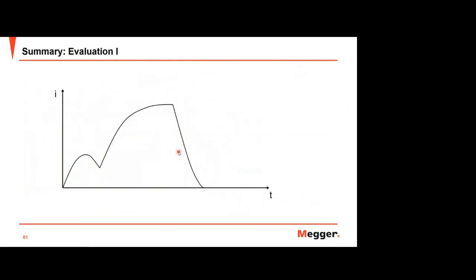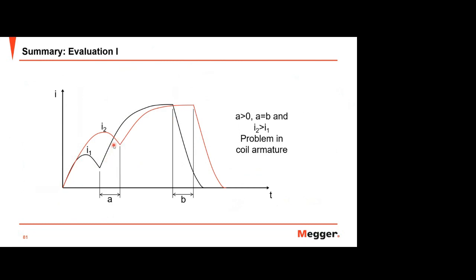And also, I can make a summary in total from many study cases. We can make a summary to analyze your tripping coil profile. So the first evaluation: if you see this characteristic compared to the reference result, if the peak one is higher than the previous peak one, I1, and there is also a delay before the buffer condition, this is the latch position. So the problem is the coil armature, the coil itself, not the mechanical link, because you can see this affects the coil part. If you see from this point to this point it will be the same. So if peak I2 is higher but the distance between A and B is the same, the problem is in the coil armature. This is the first evaluation.